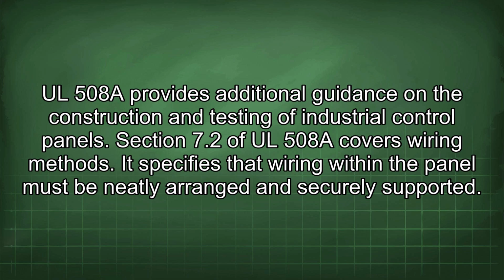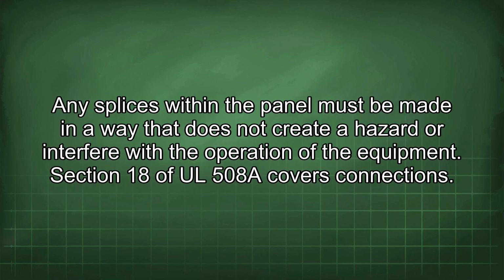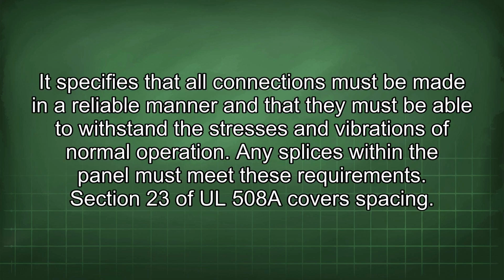UL 508A provides additional guidance on the construction and testing of industrial control panels. Section 7.2 of UL 508A covers wiring methods. It specifies that wiring within the panel must be neatly arranged and securely supported. Any splices within the panel must be made in a way that does not create a hazard or interfere with the operation of the equipment. Section 18 of UL 508A covers connections. It specifies that all connections must be made in a reliable manner and that they must be able to withstand the stresses and vibrations of normal operation. Any splices within the panel must meet these requirements.